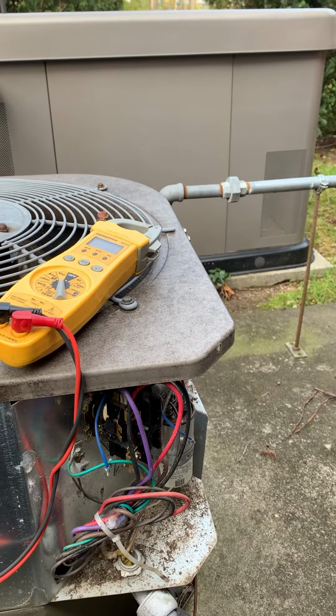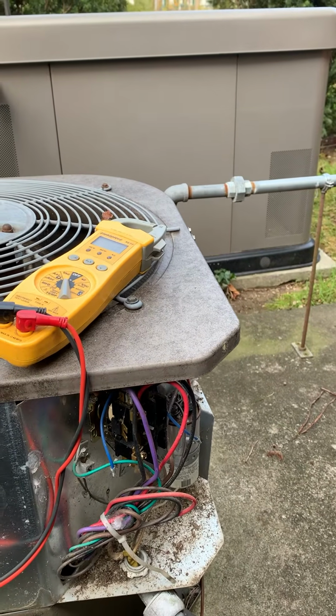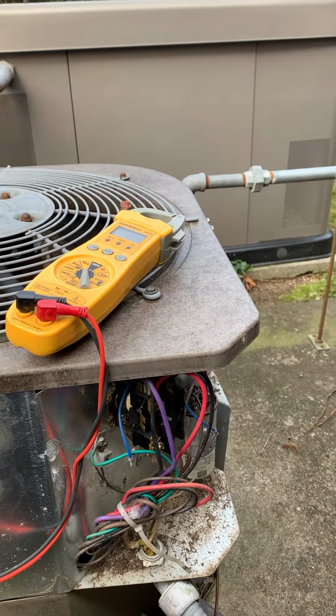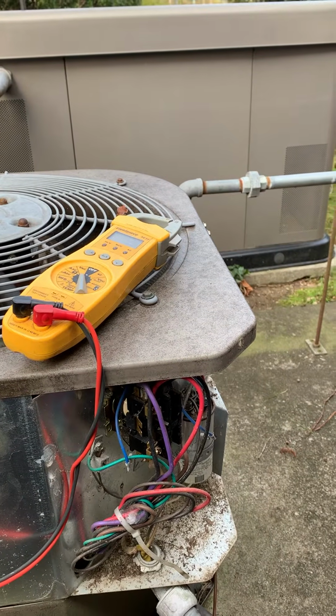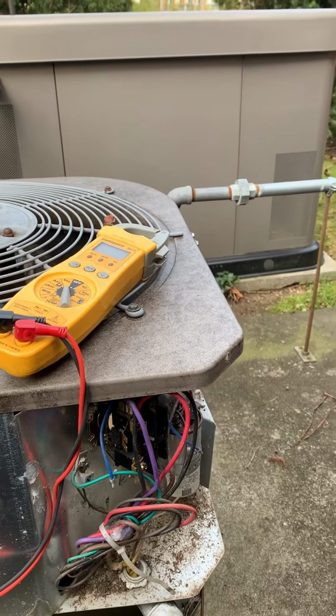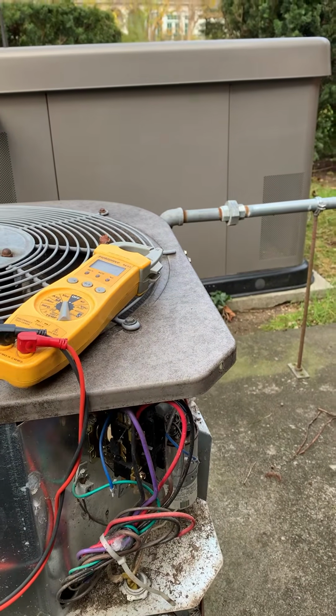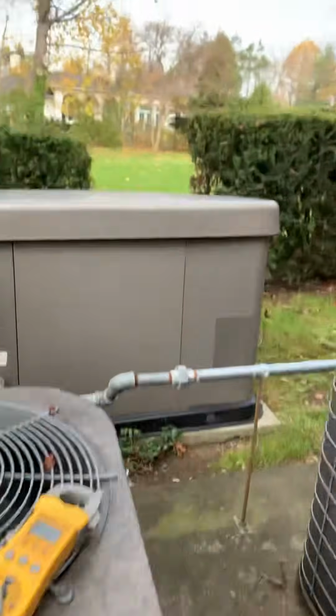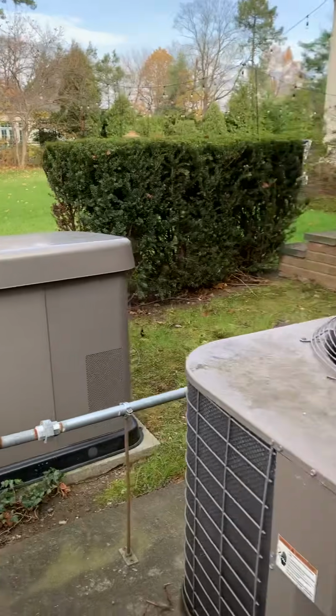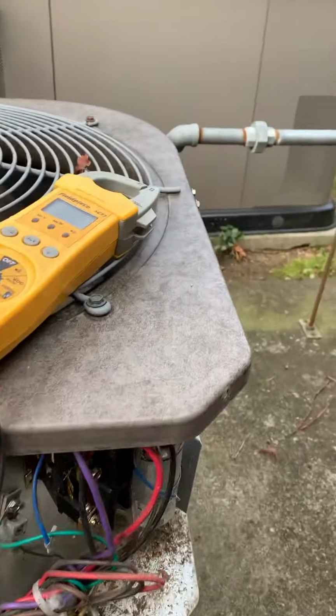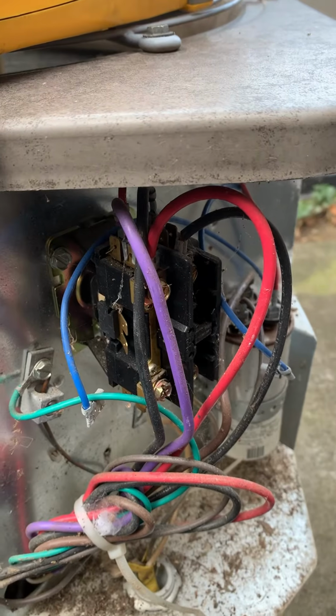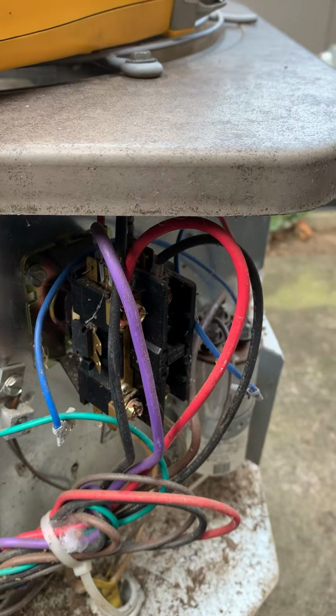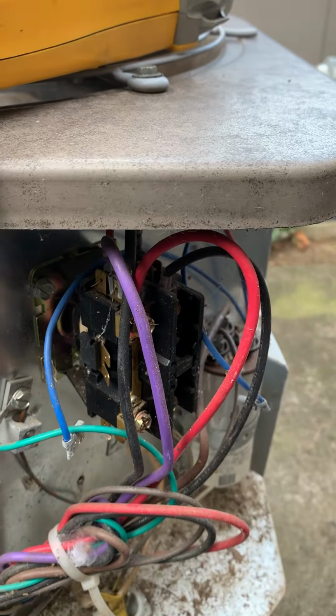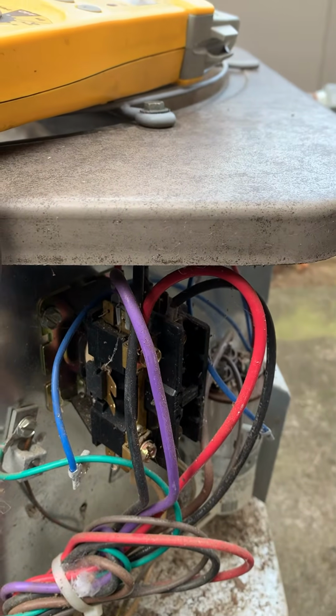Anyway, so I reset it, heat turns on, no problem. All right, shut it down, put the AC on, and all of a sudden my board light starts going crazy, starts flickering, and then all of a sudden it pops. So I come outside, okay? I come outside to this backyard with the generator and a couple units here, and I find this contactor. I pull off the low voltage onto the coil, and then I turn the unit back on, AC blower goes on, everything is fine. So once I put this back together, I'm sure it's going to pop again.